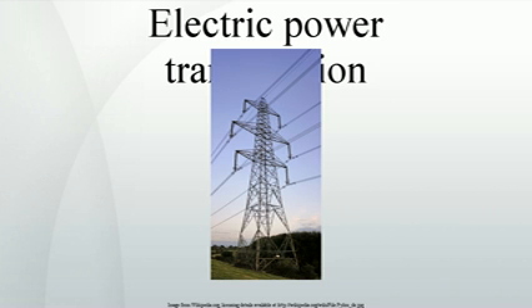Transmission grid exit. At the substations, transformers reduce the voltage to a lower level for distribution to commercial and residential users. This distribution is accomplished with a combination of subtransmission, 33 kV to 132 kV, and distribution, 3.3 to 25 kV. Finally, at the point of use, the energy is transformed to low voltage, varying by country and customer requirements. See mains electricity by country.